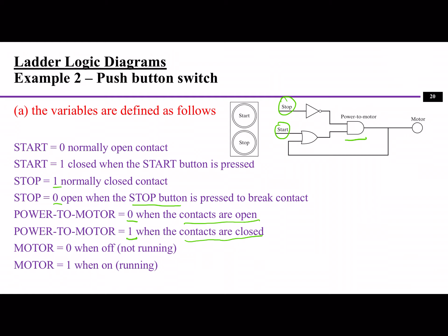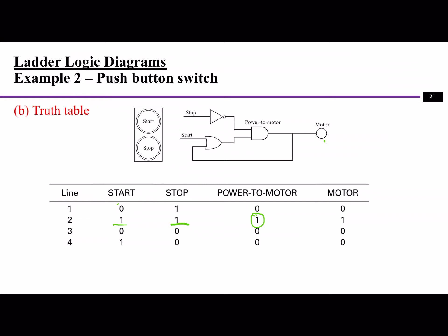Now let's look at the truth table. The truth table will help us understand the logic and the values. First we need to come up with all the combinations of those scenarios. So one scenario is line 1, when the start is taking value of 0 and stop is taking 1, and line 2 is both taking 1, and line 3 both are taking 0, and line 4 when start takes 1 and stop takes 0. Because the power to motor is the AND, it only takes the value of 1 when both stop and start are taking the value of 1. The motor's function is the same as the power to motor, because power to motor is the only one contacting the motor.